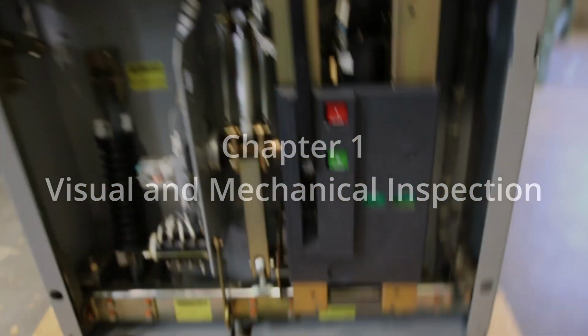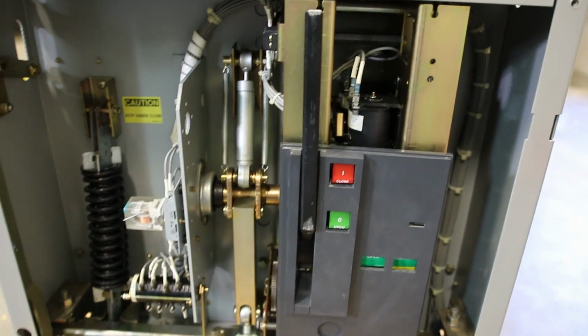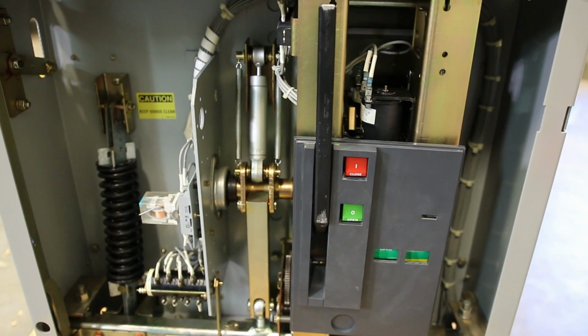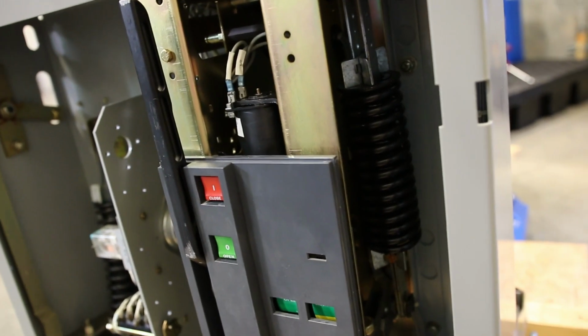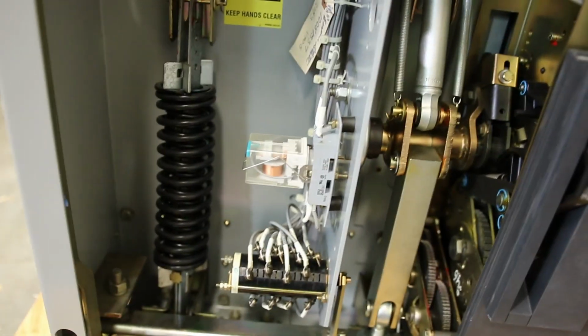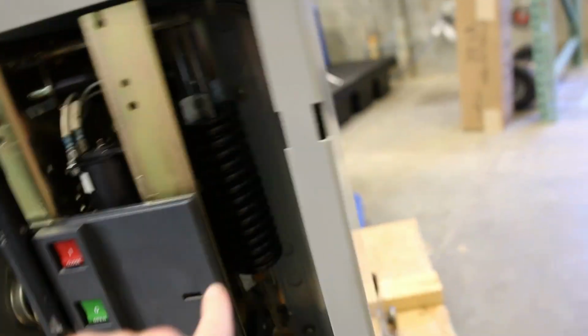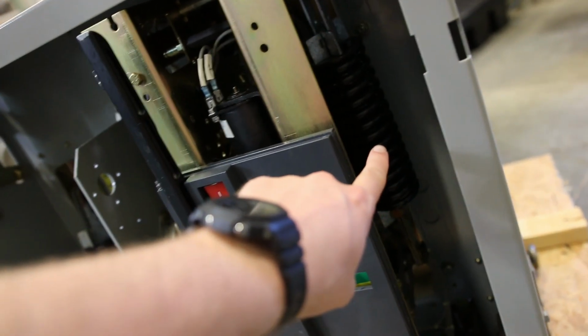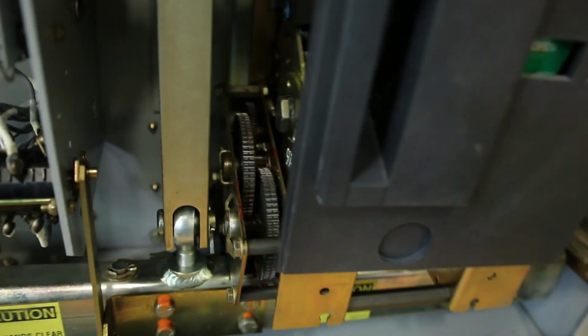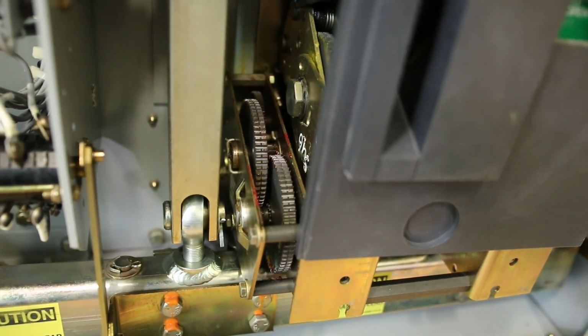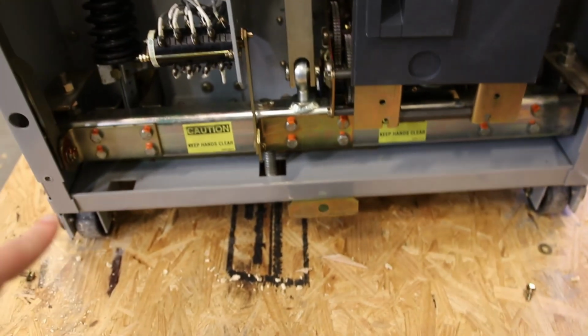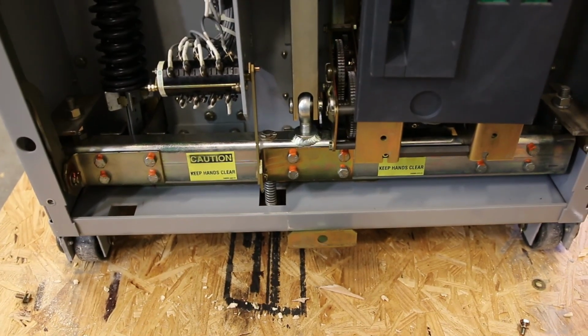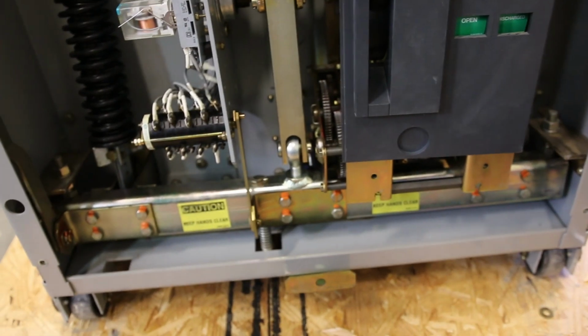Let's take a quick tour of the inside of one of these breakers. Lighting is a little bit weird. We've got our trip and close springs. So those are what store the energy. That's that guy and that guy. That's what store the energy to obviously trip and close the breaker. That's how it operates so quickly. There is a charging motor. We want to make sure that there's a decent amount, a thin film of grease on the gears out of the charging motor. This bar across the bottom is actually what moves the physical contacts themselves.